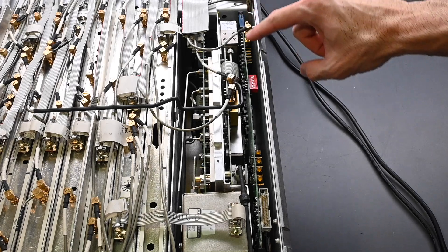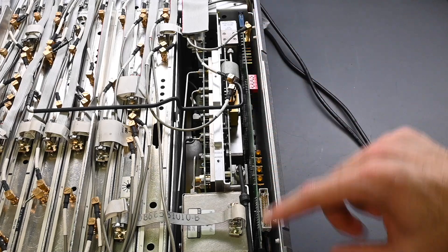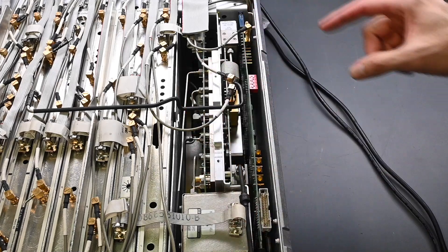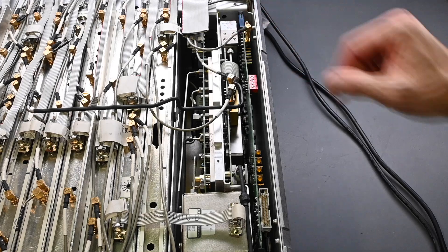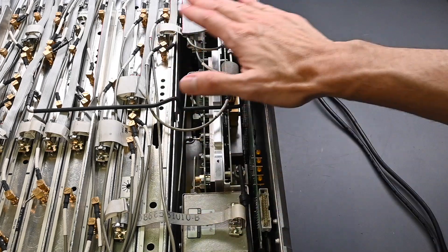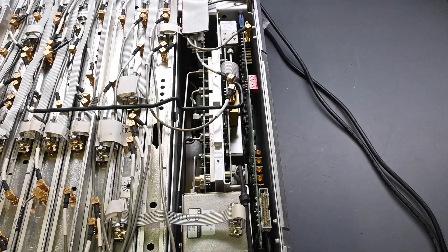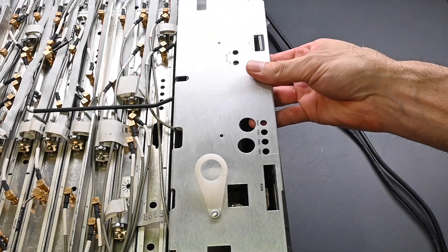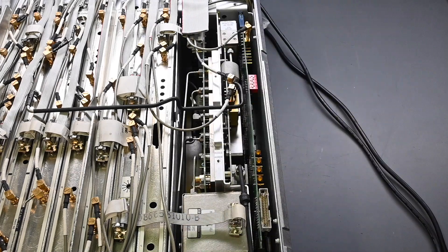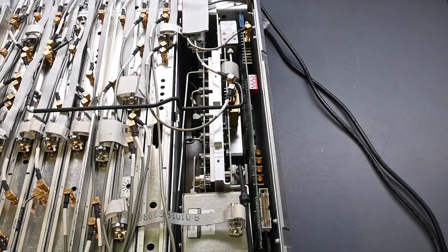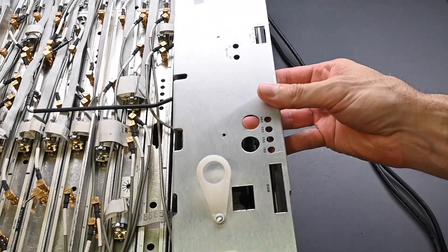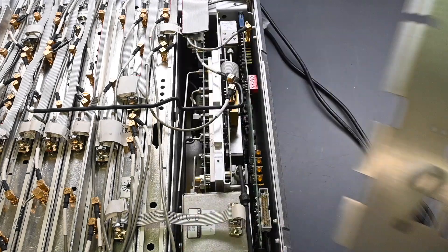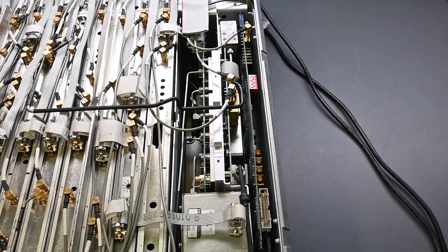All right, so this is a control board along the edge right here, so it just plugs in, it lifts straight out, have to remove this coax cable as well. Now normally this section right here is covered by this metal shield, so this fits in here like so, and of course this metal shield, to be able to remove it, these two coax cables would have to be removed as well, but I already had this metal shield taken out because of the other work that was being done on the instrument.